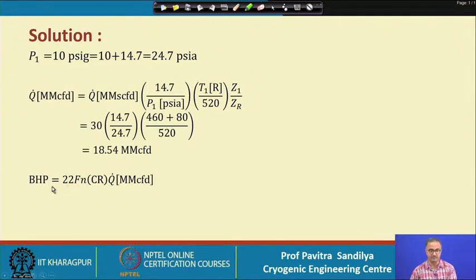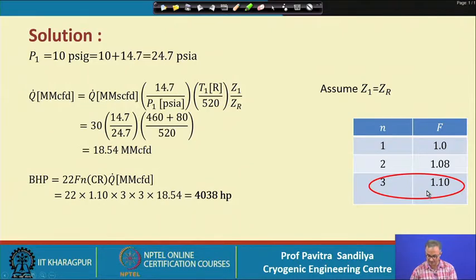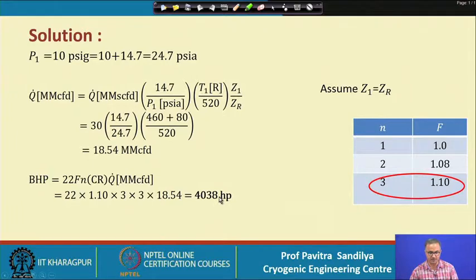We then use the expression for brake horsepower (BHP). From a table giving different values of the factor F for different numbers of stages, for 3 stages we get F = 1.10. Plugging in F = 1.10, N = 3, the compression ratio CR, and the flow rate Q from the previous expression, we arrive at the final value of the brake horsepower for this compression.